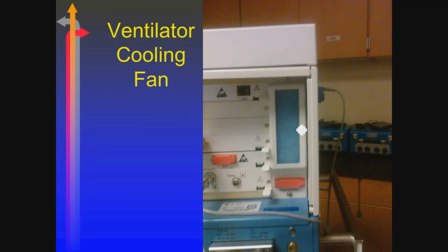It's not anything coming in contact with the patient, but again, if it gets clogged, just like the filter on your furnace at home, do you guys know you have a furnace filter? If they're not changed, eventually it's causing more wear and tear on the furnace, or in this case, the ventilator fan, because it's blocked off. So you want to be able to clear it off. And in the process, then it doesn't cool, and it can overheat, and when the electronics get overheated, bad things happen. And since this is a life support device, you kind of don't want to have bad things happening.